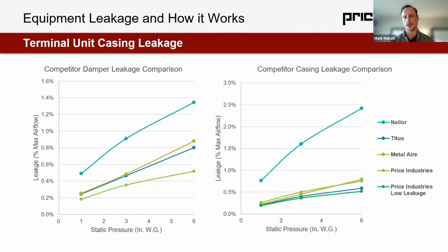Casing leakage, though, is much more important to actual leakage performance. The damper leakage, the damper is usually open. It's very infrequently closed all the way. It happens, but most commonly the damper is open and operating somewhere from 25% open to 100% open. Casing is what really matters. And when we look at casings, Titus, Metal Aire, and Price, once again, perform very, very similarly. Nailor's a little bit more elevated, leaks a little bit more through their standard casing.